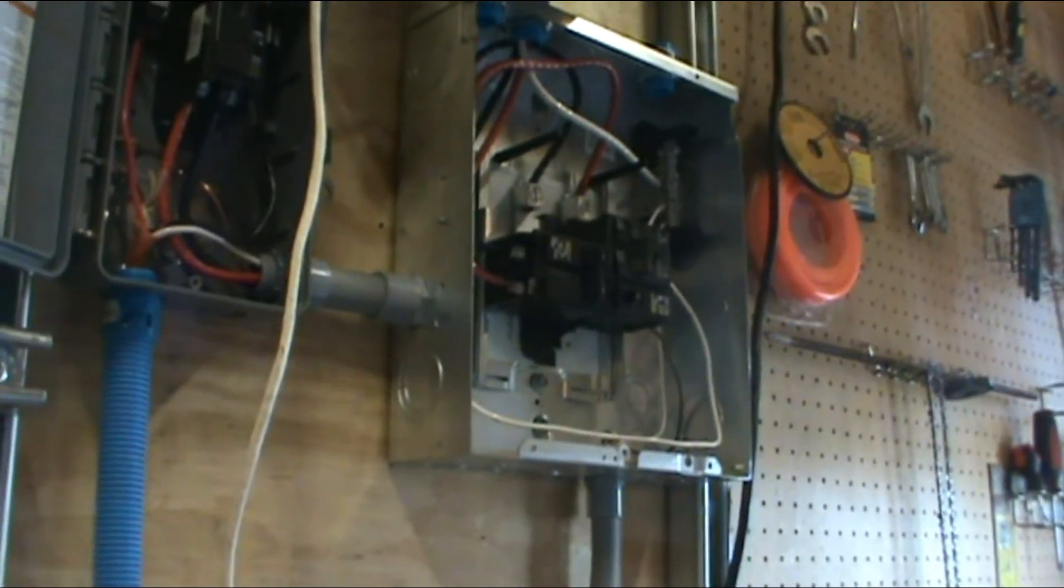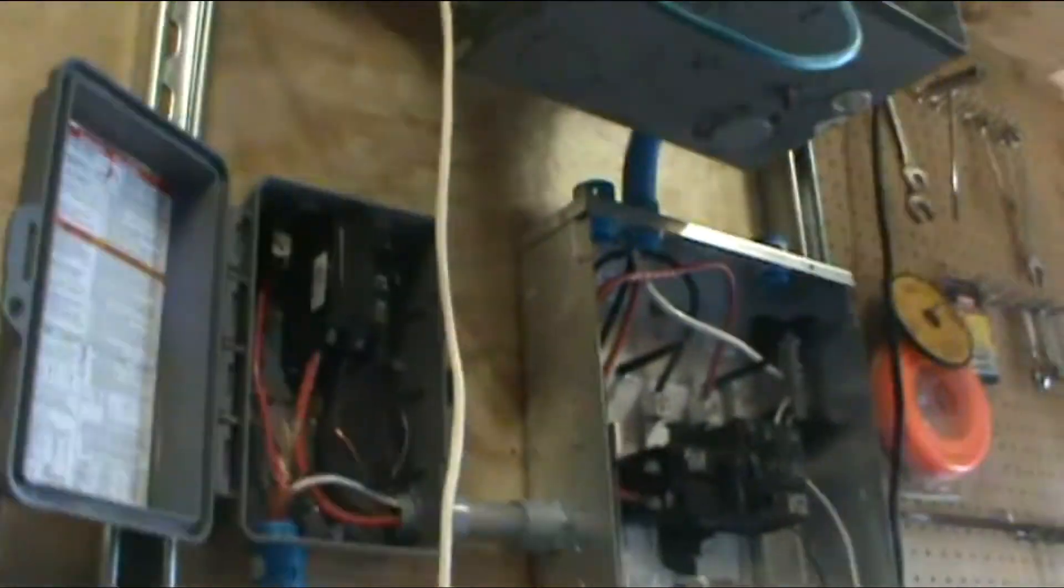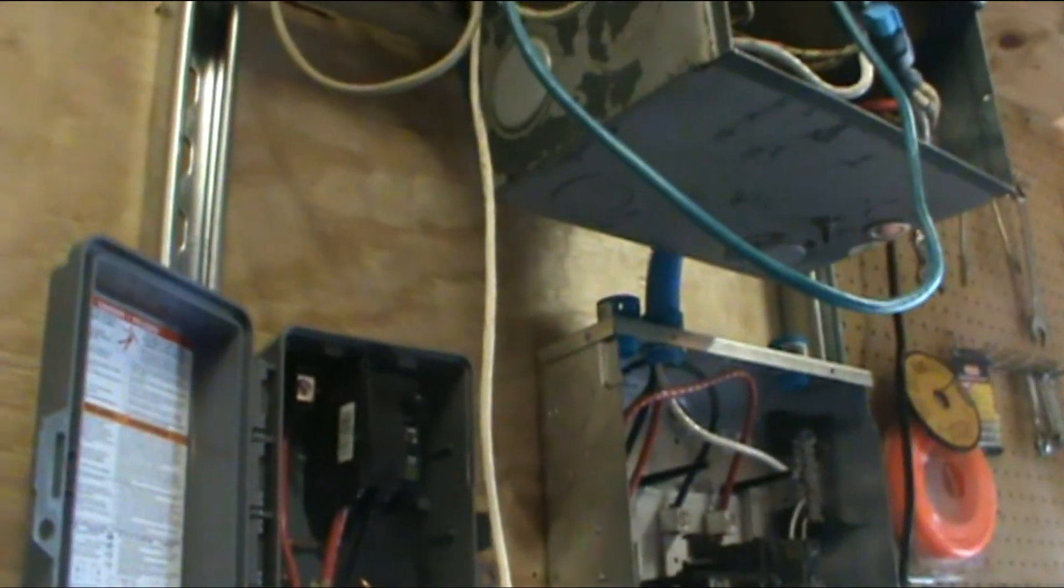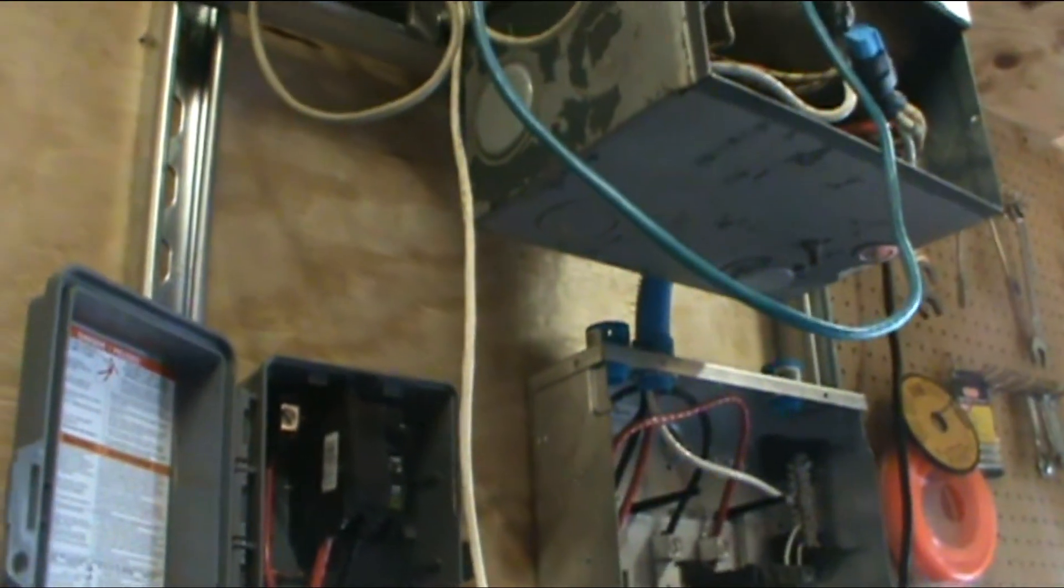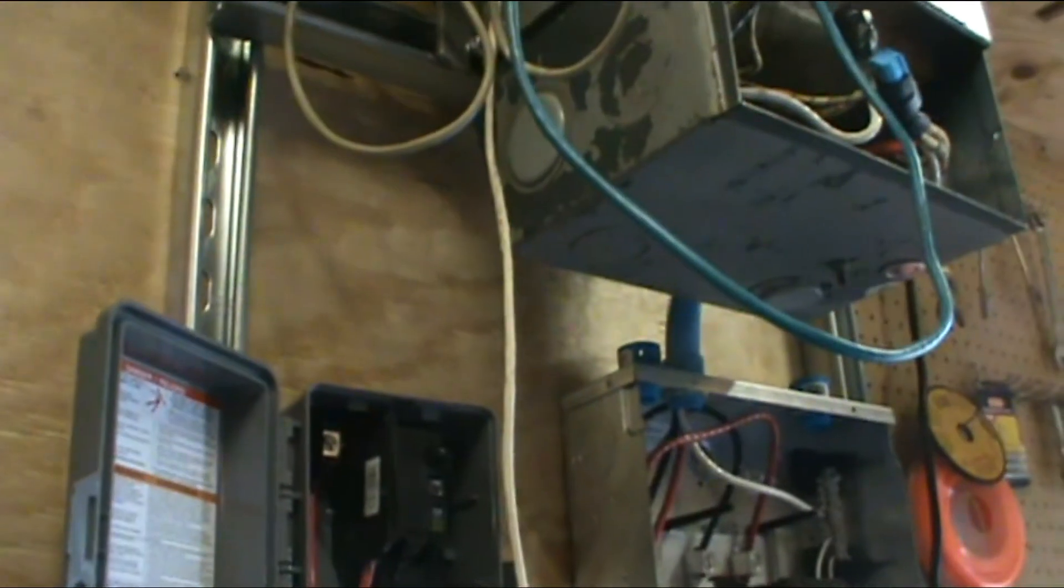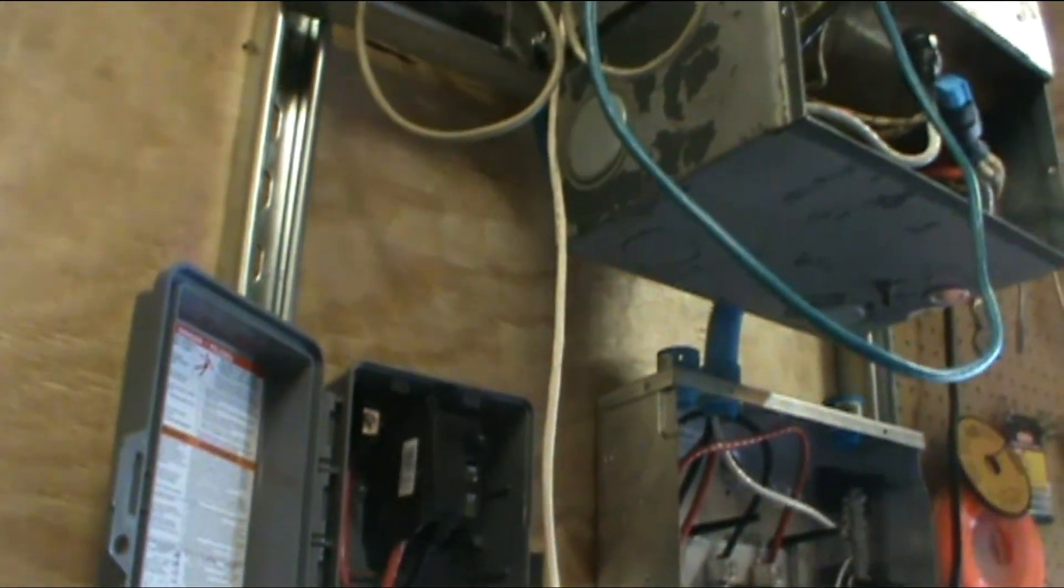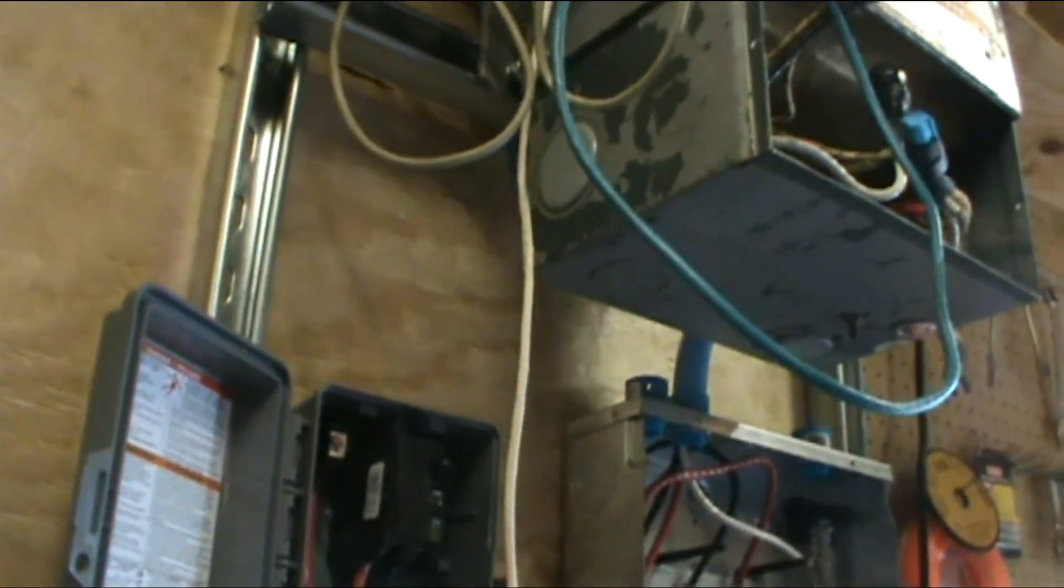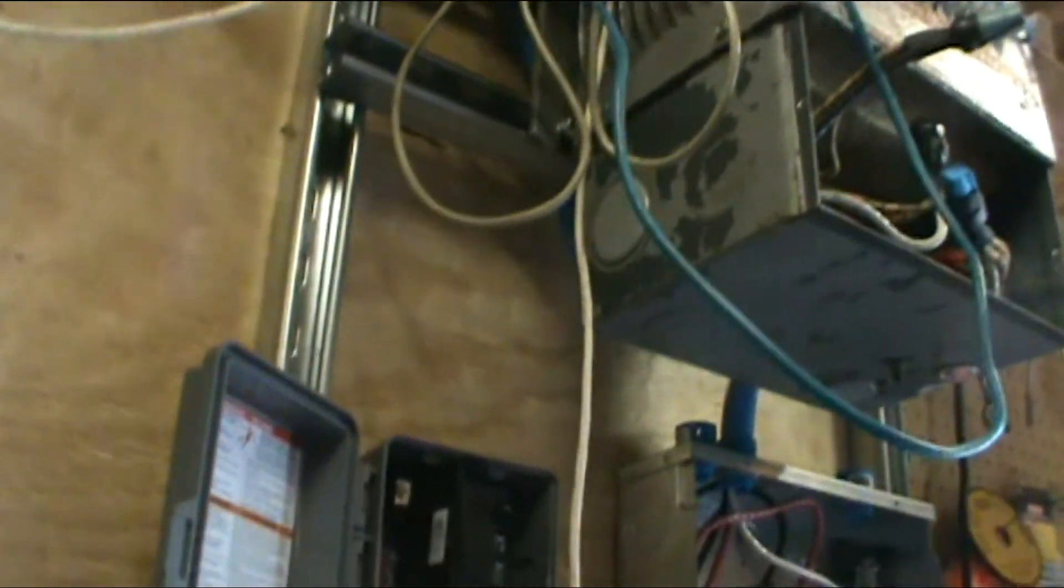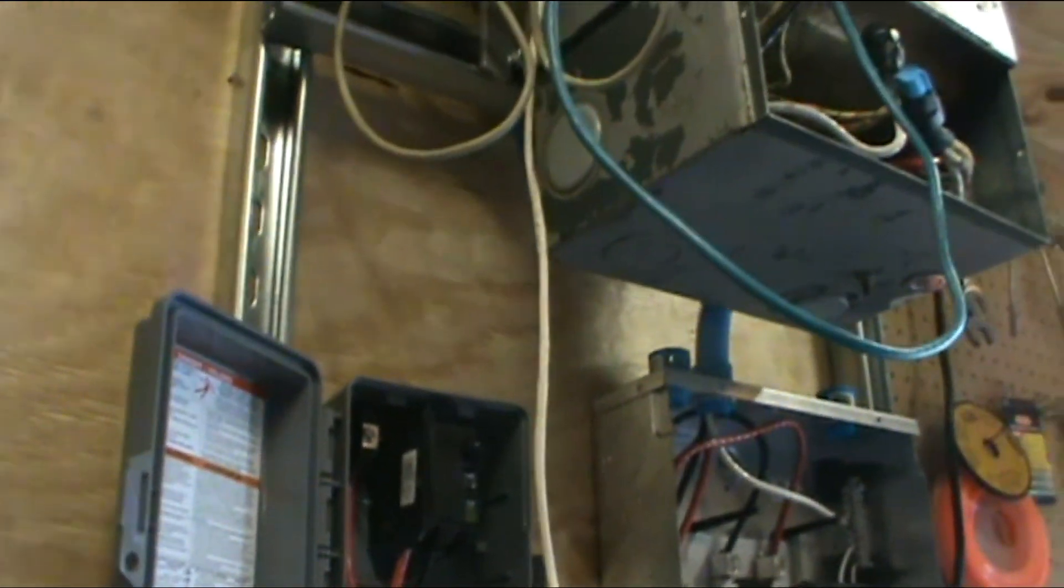I've got a 30 amp double throw at the pole and another 30 amp double throw right there. It doesn't matter what these breakers are, if anything gets overloaded that breaker trips first. That's 60 amps total, I can use 30 amps on each leg as long as it's balanced. But not everything is going to be on at the same time, so we don't have to worry about using all 60 amps.